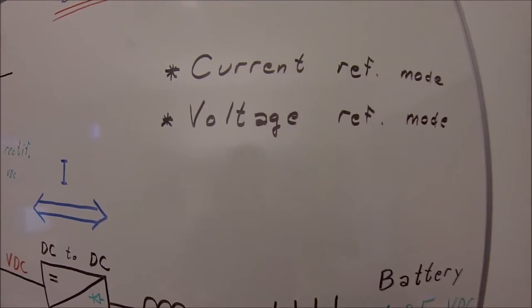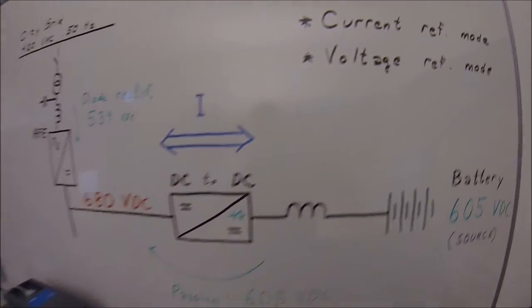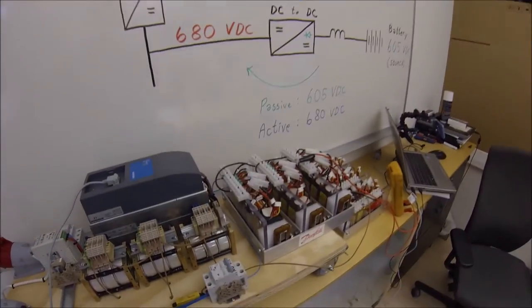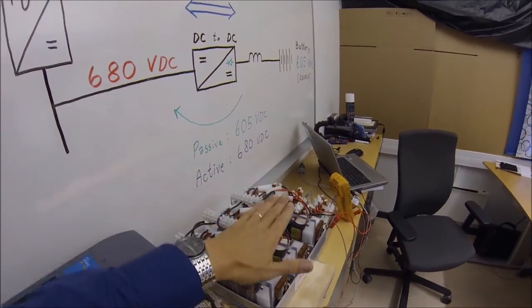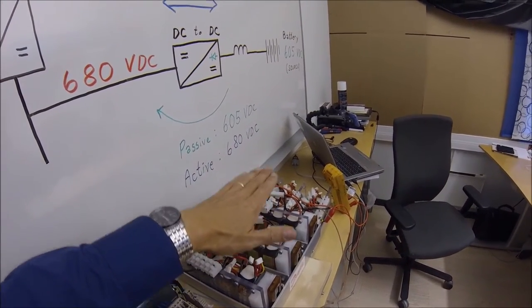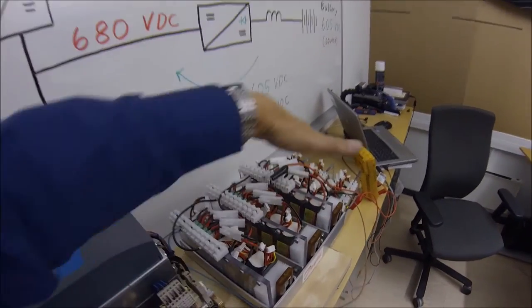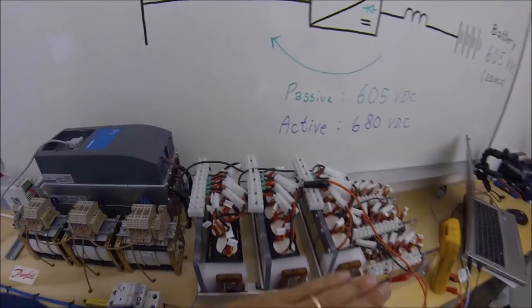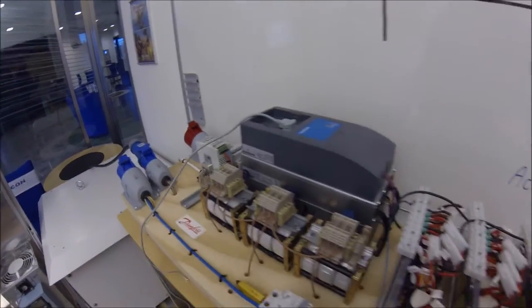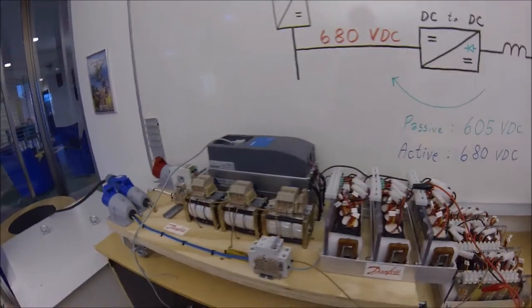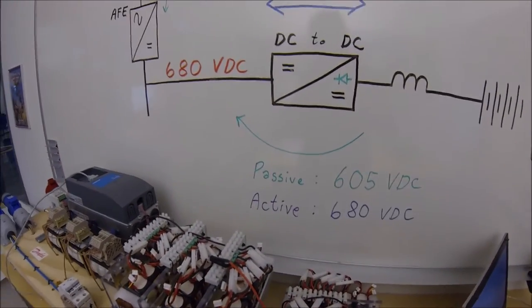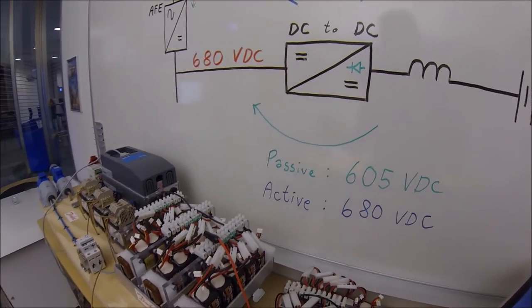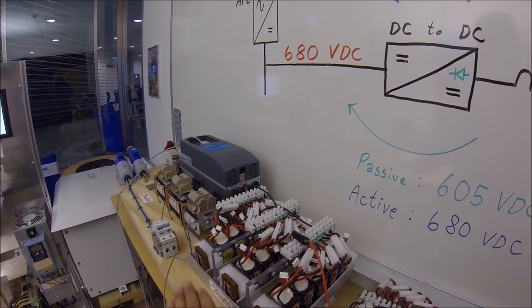We are now going to look into voltage reference mode running. The voltage reference mode means that we are aiming for keeping a specific voltage on the battery. If we try to force the voltage up, then the current will flow into the battery. If we try to force the voltage down, we'll go in opposite direction. We don't have that much control of the current. Of course, you can run it against some current limits. But basically, we just aim for a certain source voltage.